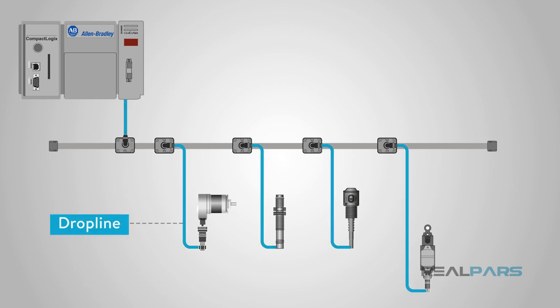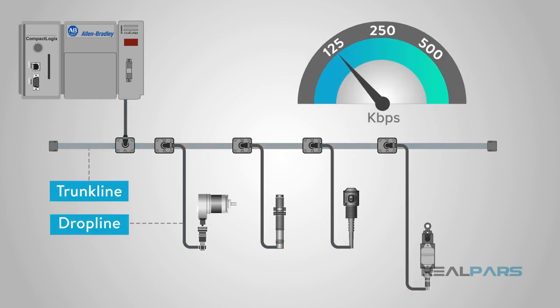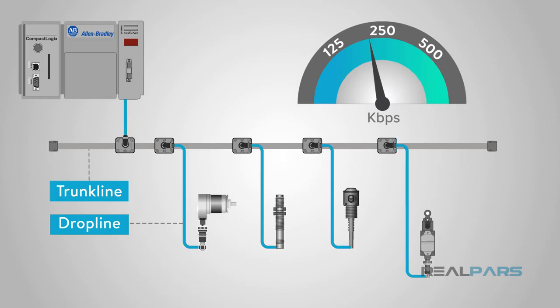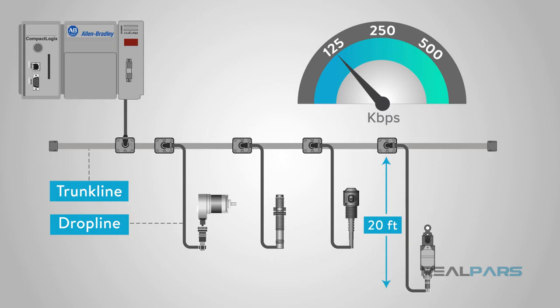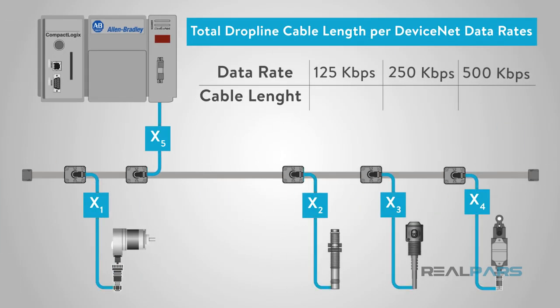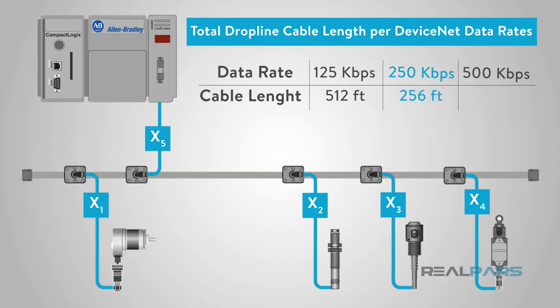The drop lines connect the devices to the trunk line, and the data rate you choose determines the total drop line length allowed. The maximum cable distance from any device to the trunk line is 20 feet. The maximum total drop length for each data rate is 512 feet at 125 kbps, 256 feet at 250 kbps, and 128 feet at 500 kbps — showing that higher data rates yield shorter distances and lower data rates allow farther-reaching capabilities.